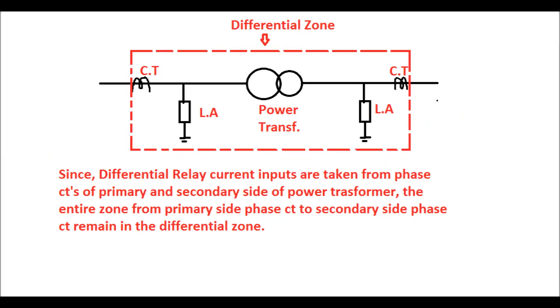The differential zone of the power transformer is shown in this diagram. Between the CTs on either side of the power transformer, there exist the HV and LV windings. Since the differential current inputs are taken from the CTs on the primary and secondary sides, the entire zone from the primary-side CT to the secondary-side CT remains within the differential zone. If any fault occurs within this zone, the relay shall operate. Any fault outside this differential zone produces a through fault current, and the relay must maintain a stable condition during through fault current.